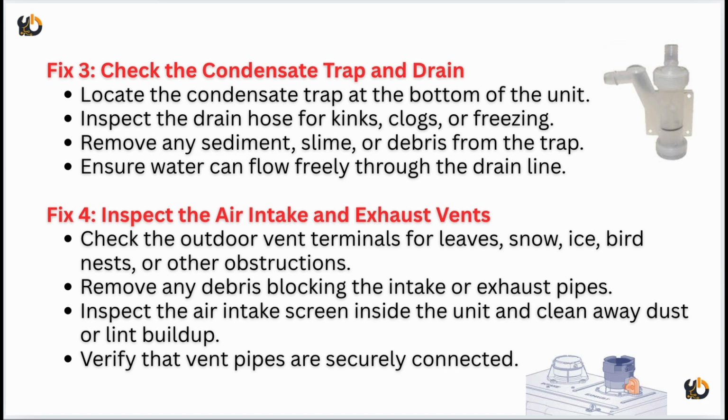Fix 4. Inspect the air intake and exhaust vent. So check the outdoor vent terminal for leaves, snow, ice, bird nests or other obstacles. Then remove any debris blocking the intake or exhaust path, and inspect the air intake screen inside the unit and clean away dust or lint buildup. Now verify that the vent pipes are securely connected.